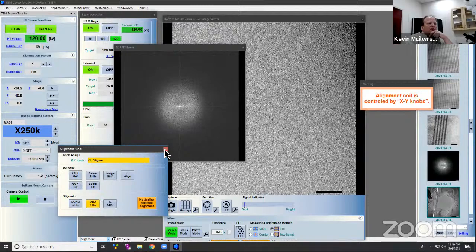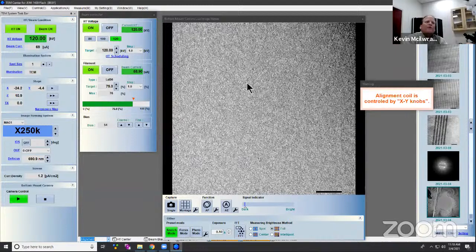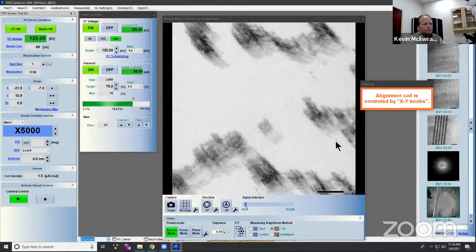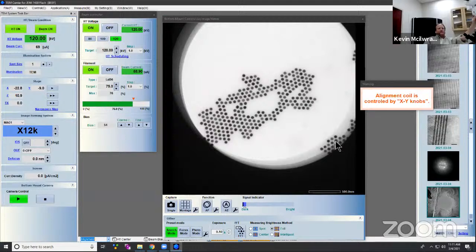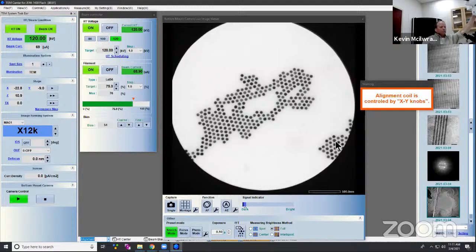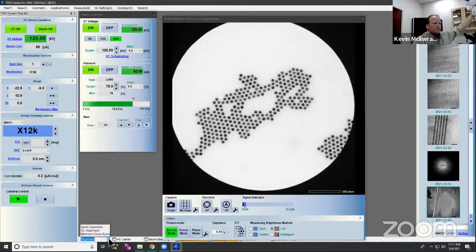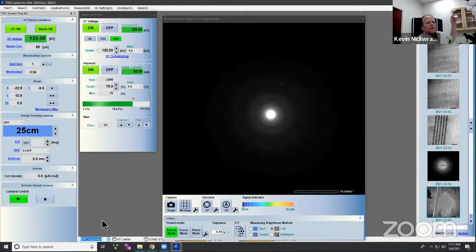So now on this sample, we're going to do something a little different with the diffraction. If I want to look at a polycrystalline pattern, I'll put in my diffraction aperture, right? And I'll put in kind of a big one. I'll get a lot of crystals in this. And I will turn off that, and then I will switch to diffraction mode, pull that out.